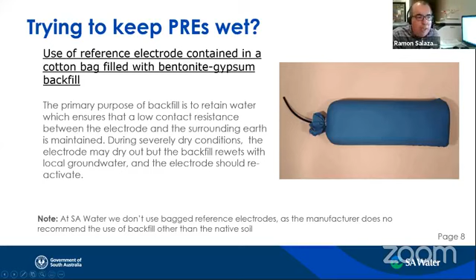Now, in terms of evaluation of reference electrodes, we have in NACE a TM0211, and they provide a method to evaluate the durability of reference electrodes. However, what they measure is the copper sulfate leaching out of the reference electrode or chloride contamination. However, they say in section 1.4 that they are not measuring the tendency to dry out, so it's not addressed by this test method.